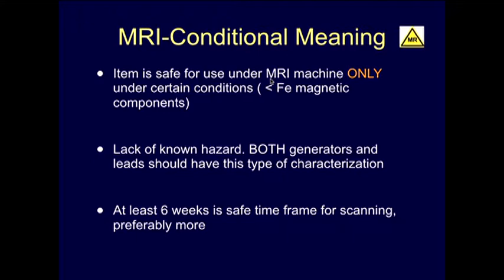And those particular conditions for devices and for pacemakers are that they should have low ferromagnetic components. St. Jude and all these companies have focused on reducing the load of ferromagnetic or iron magnetic components to have less attraction by the magnet. There is no known danger, and both the generator as well as the electrodes should have the same characterization. If I replace the electrodes with a conditional one, but the box is not conditional, that turns the system non-conditional, and that completely changes the way we approach those patients. Generators and electrodes must be conditional.